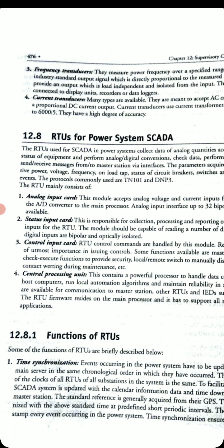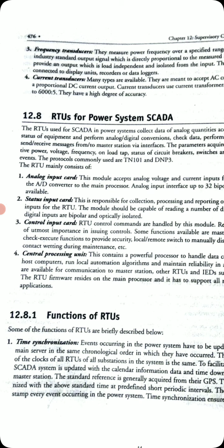Some functions available are master trip and close relay, and select check and execute functions to provide security. A local remote switch to manually disable relay coil power and contact wetting during maintenance. These are the things for the control input card. Then the central processing unit, CPU. This contains a powerful processor to handle the data collection and deliver it to the host computer, to run local automation algorithms and maintain reliability in a substation.